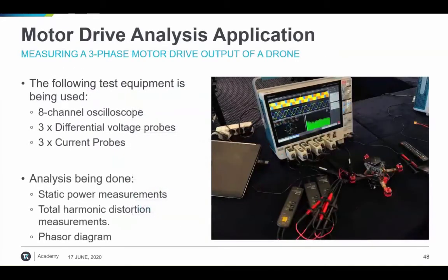Before the live demo, here is an interesting motor drive application worked on previously. Voltage and current probes were connected to one motor of a drone to make static power measurements on the scope — including RMS voltage and currents, some power measurements, total harmonic distortion measurements, and looking at the phasor diagram as well. That concludes the presentation portion, and now we move on to the live demo.